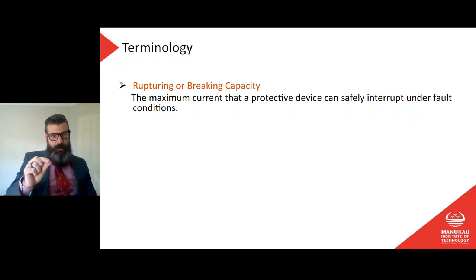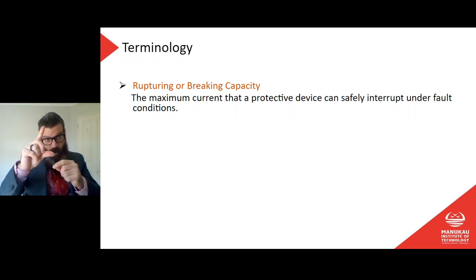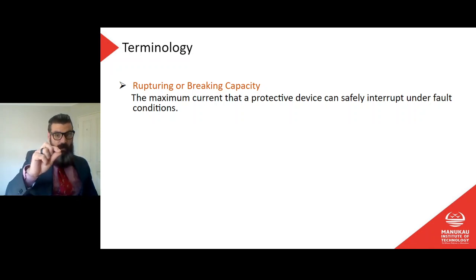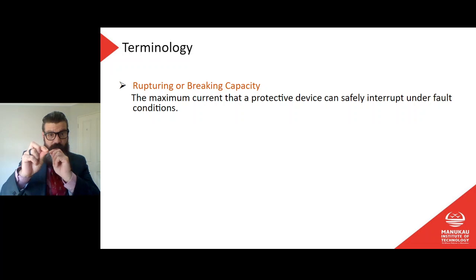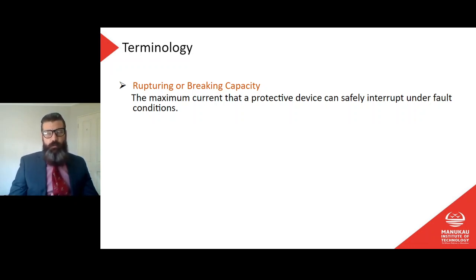Remember that we talk about, like, if we put too much current through it, then the little contacts that are supposed to open when the circuit breaker trips might just weld together. If we get so much current through there so quickly and they just weld together, then the circuit breaker won't trip because it will physically be welded closed. So that's our breaking capacity or rupturing capacity. And remember, we talk about that in terms of our prospective short circuit current.